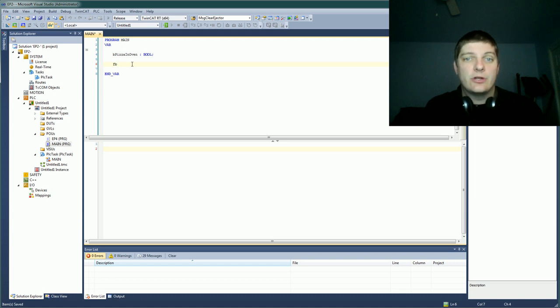instantiating a function block here. And so what this does is we'll make a timer called a TON, and it will accumulate time anytime its input is true, and it'll set an output when it's done. So it handles all the scan time, converting that to real time, which is really nice. So I sometimes like to put comments here and just explain what it is. So if it's not perfectly obvious, my timer's not the greatest name, so I'll tell it, it's cook time.